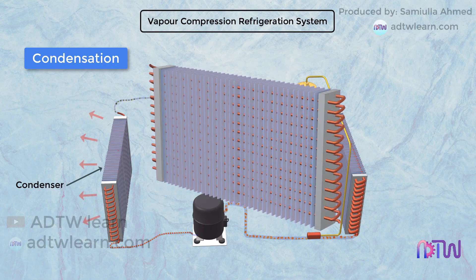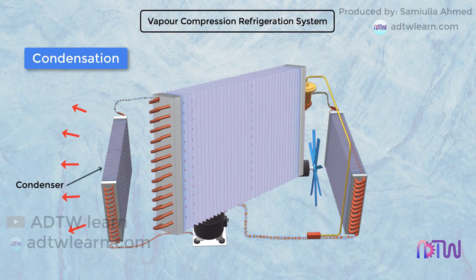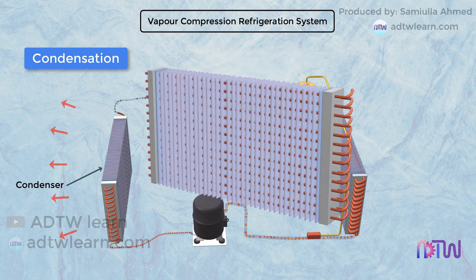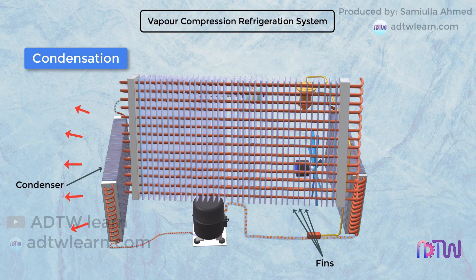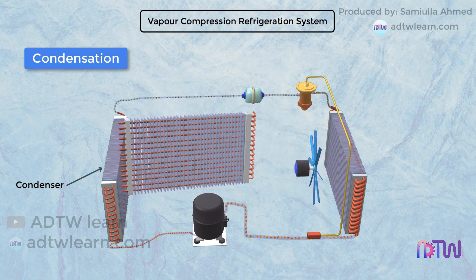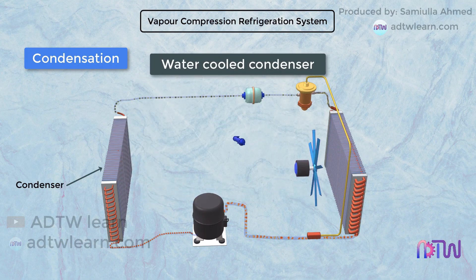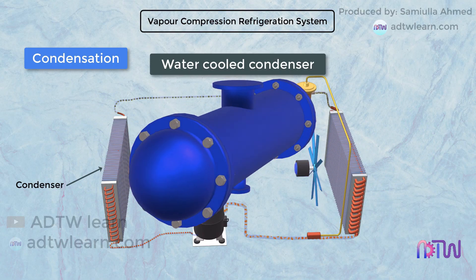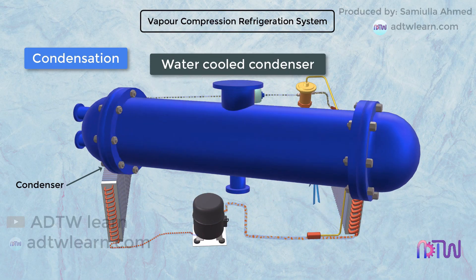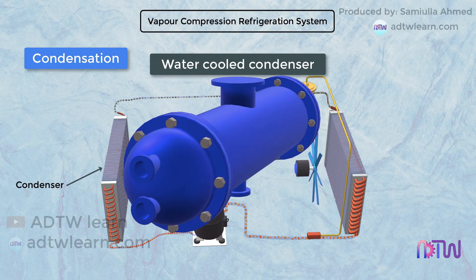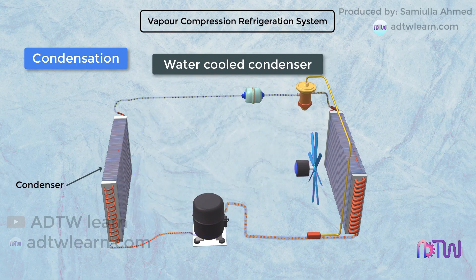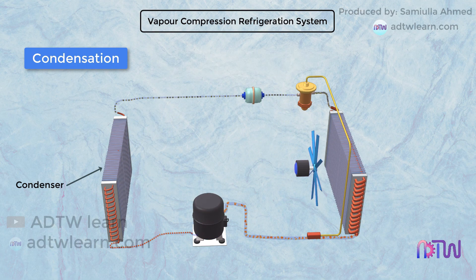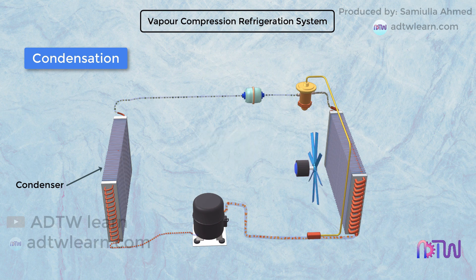Condensation of the refrigerant coming from the compressor is carried out by the condenser. The condenser is essentially a heat exchanger which rejects heat to the atmosphere. The rejection of heat can be direct to the air through fins. Another way is using water-cooled condensers, which have a cooling water supply whose function is to carry the heat from the condenser to the cooling tower, where it is further discharged to the atmosphere. The type of condenser used depends on the size of the vapor compression refrigeration system.